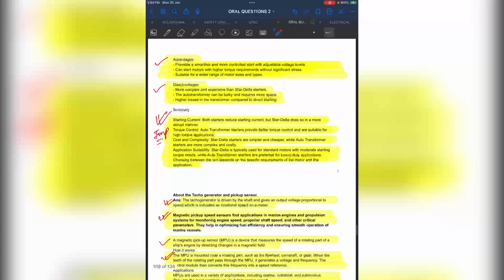And what are the advantages? It provides a smoother and more controlled start with an adjustable voltage level, because there is an adjustable voltage level with the help of the tapping, and it can start a motor with a high torque requirement without significant stress. There is no sudden changeover from star to delta like this. It is suitable for a wider range of motor types.